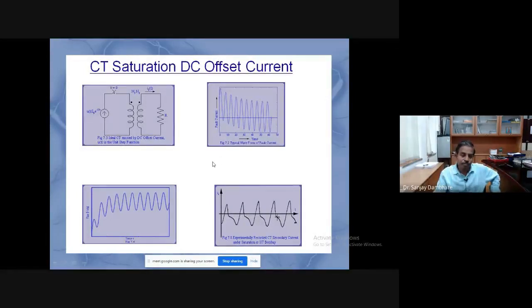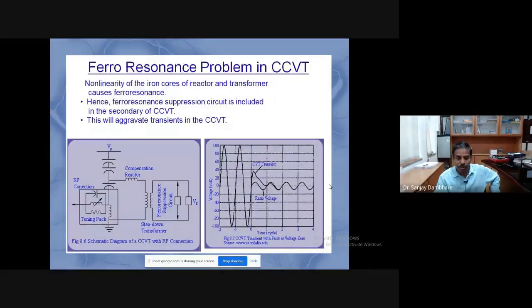But the point is that when the CT is saturated, it doesn't give the accurate replica of the primary current, and that is how the relay gets the wrong information during CT saturation. It's very crucial, because the decision of the relay depends upon the information given to the relay. So CT saturation should be avoided. There are some techniques to handle this situation: hardware compensation or software compensation. But it's very well known that power system engineers normally oversize the CT, and the oversizing of the CT will definitely mean a high cost of installation, because the size of the CT you are expecting is very huge.